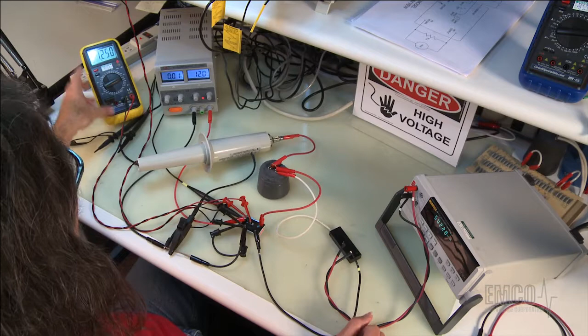And we did get a deflection on the oscilloscope probe. Now at this level it's reading about 486 volts, so the high voltage probe itself has a calibration and a linearity factor, so that comes into play when you're using a high voltage probe. We're starting to read 10 milliamps of input current. Again, this is a no-load test, so our input current should be very low, so even at 1/4 output voltage we have a fairly nominal input current. So I will go ahead and set it to half voltage.